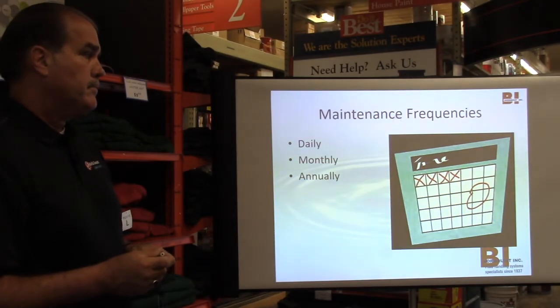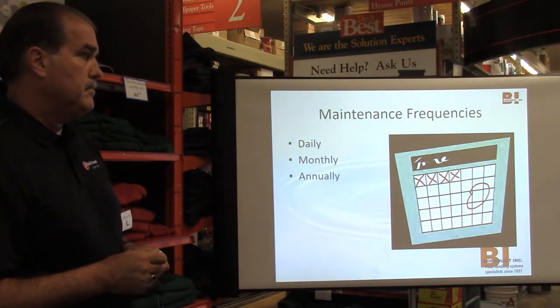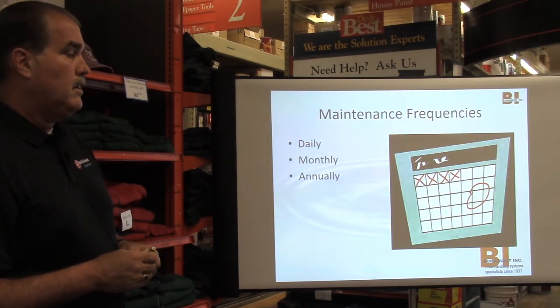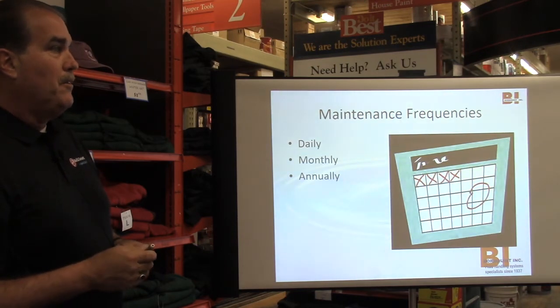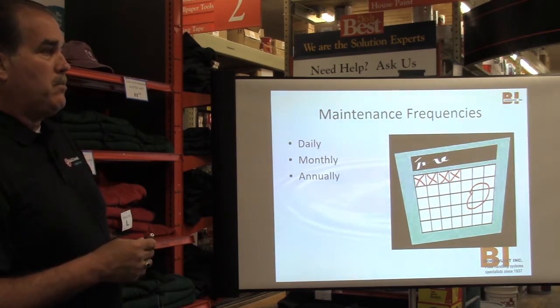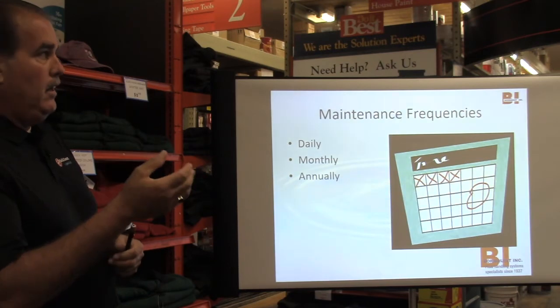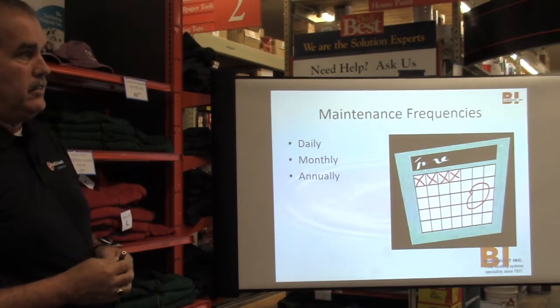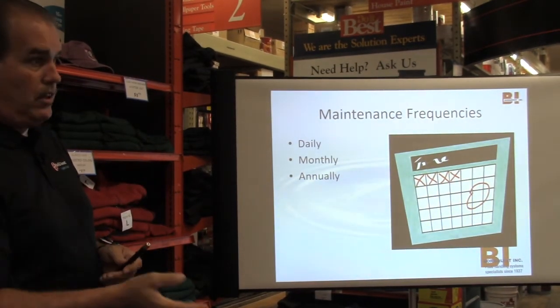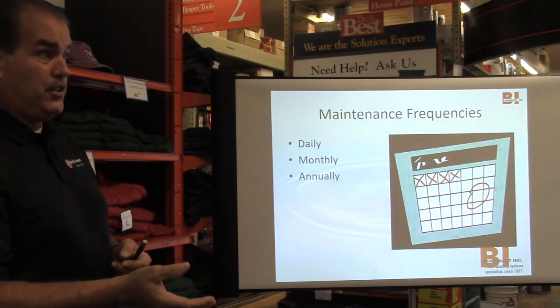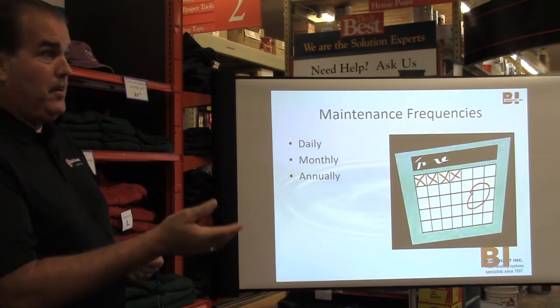What's the minimum color that you're supposed to look for when you discharge the water? Clear is clear. Till it's clear. Will it be? No. Yeah. But that's why you're flushing it. The initial flush will be, it's a dirt leg. It's a natural dirt leg, so it's going to have sediment. So you're going to see, actually, it's okay to see junk come out because that means you've been successful.